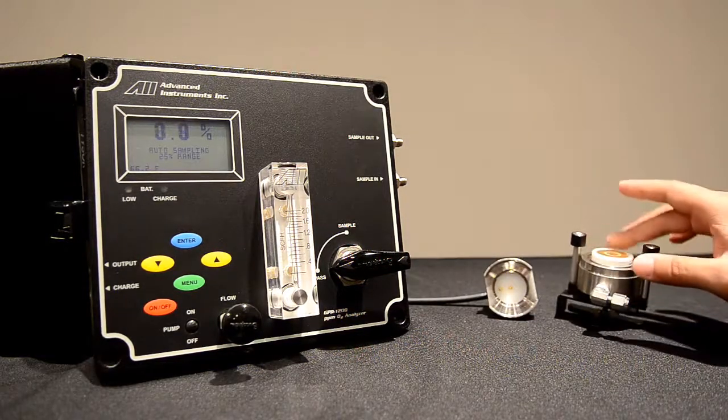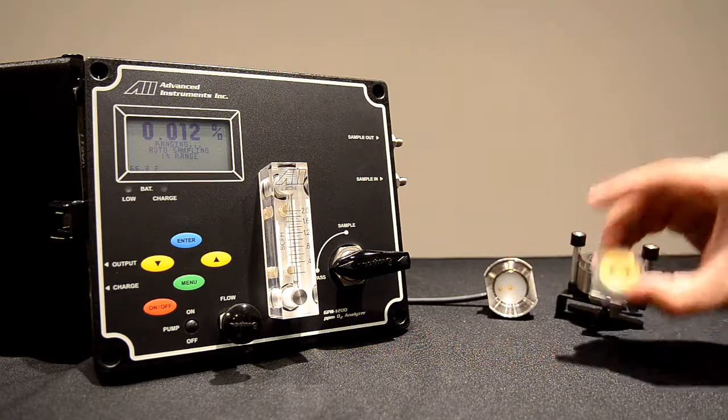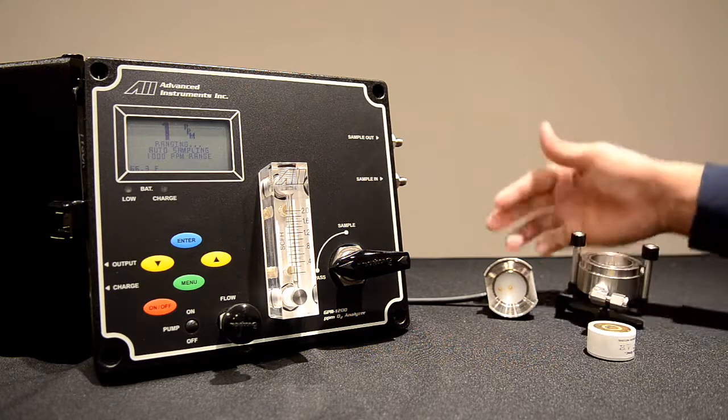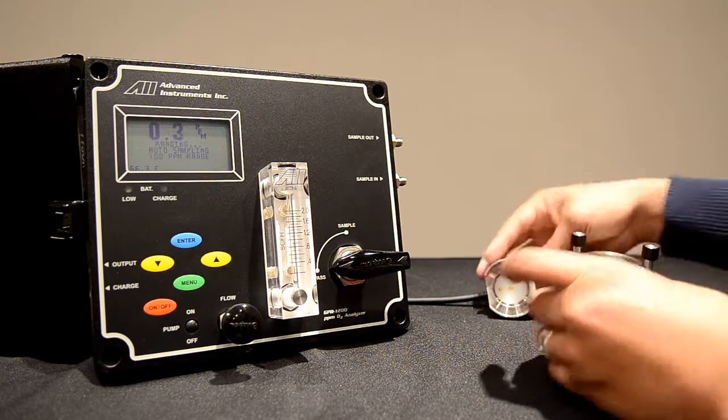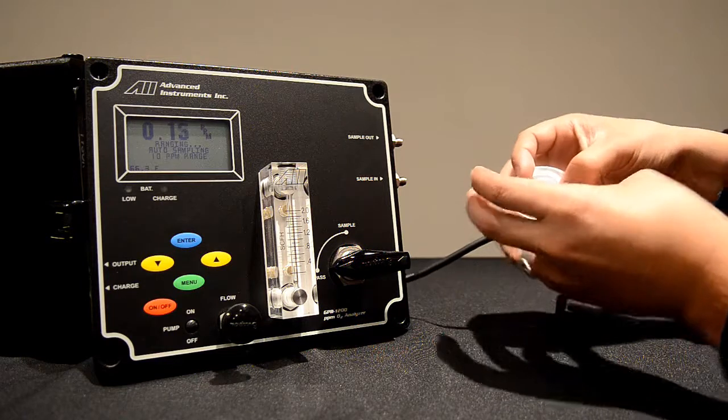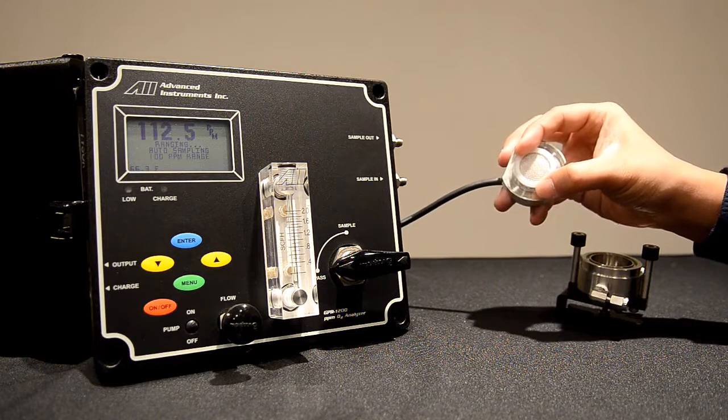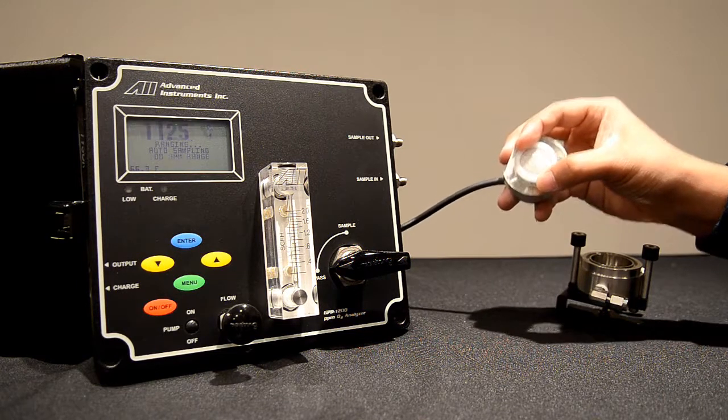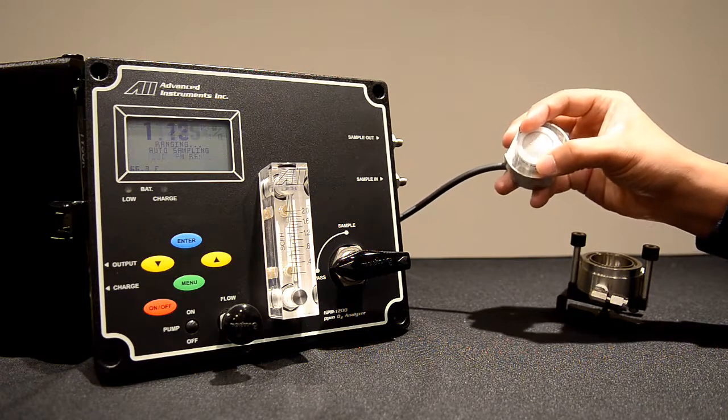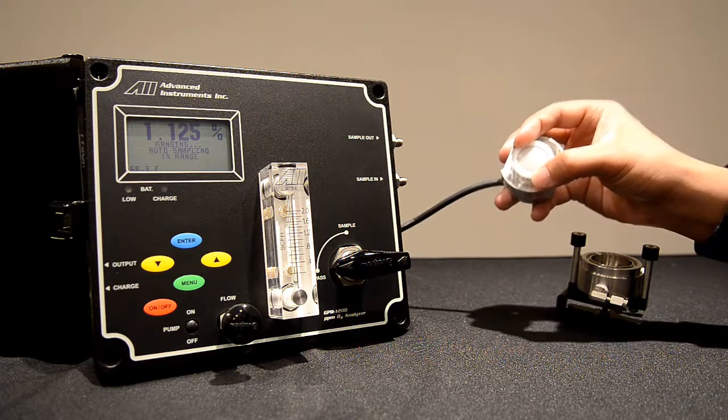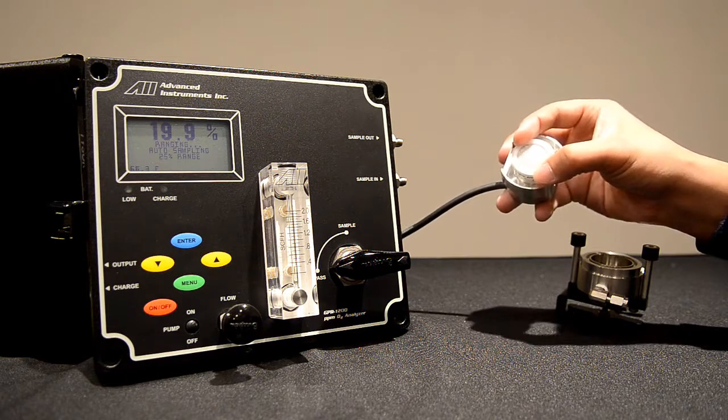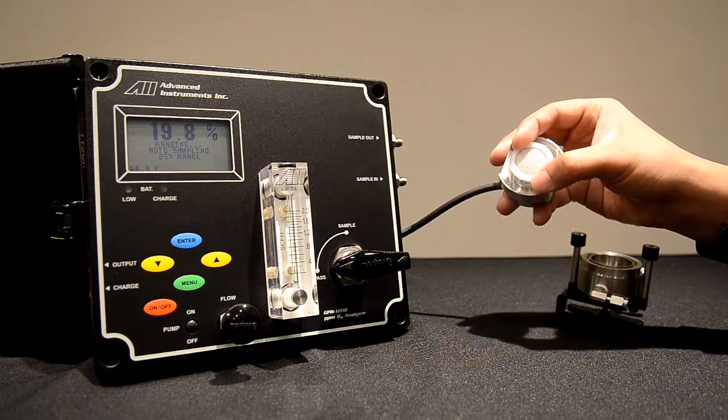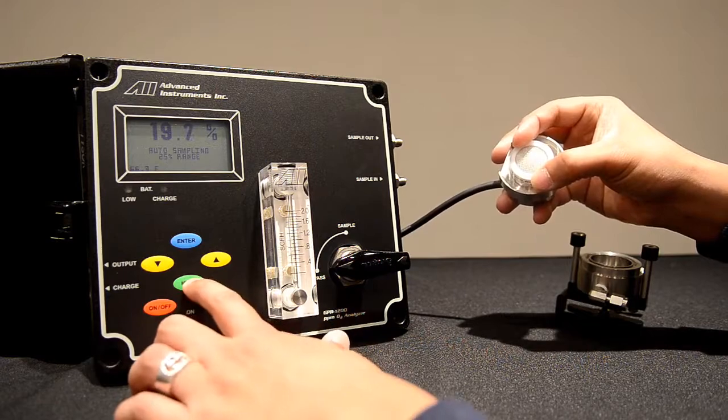As you can see, we have the sensor inside the analyzer and the top housing. The sensor will have a gold plated bottom that corresponds to the gold pins of the top sensor housing. We will place the sensor inside as so to mate the two gold parts and hold the sensor firmly with two fingers on the edges, avoiding the center of the sensor. We will now wait for the reading to stabilize for the oxygen sensor. For a brand new sensor, the oxygen reading should be anywhere between 17% to 25%. These will be acceptable ranges for calibration.